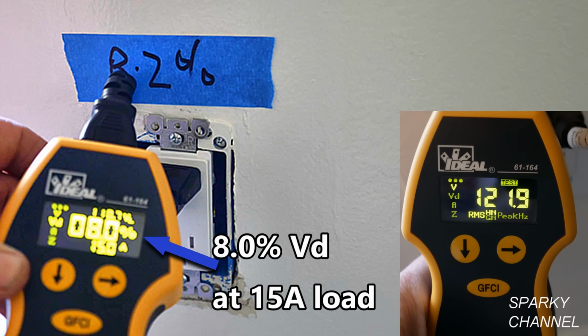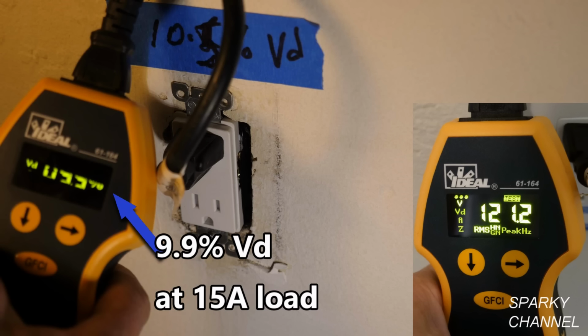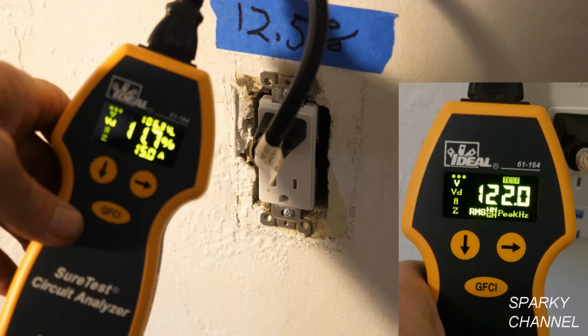The third receptacle on the circuit now reads 8% voltage drop at a 15 amp load, down from 8.2% with the no load voltage at 121.9 volts AC. The fourth receptacle on the circuit now reads 9.9% voltage drop with a 15 amp load, down from 10.5% with the no load voltage at 121.2 volts AC. The fifth receptacle now reads 11.7% voltage drop at a 15 amp load, down from 12.5% with the no load voltage at 122 volts AC.